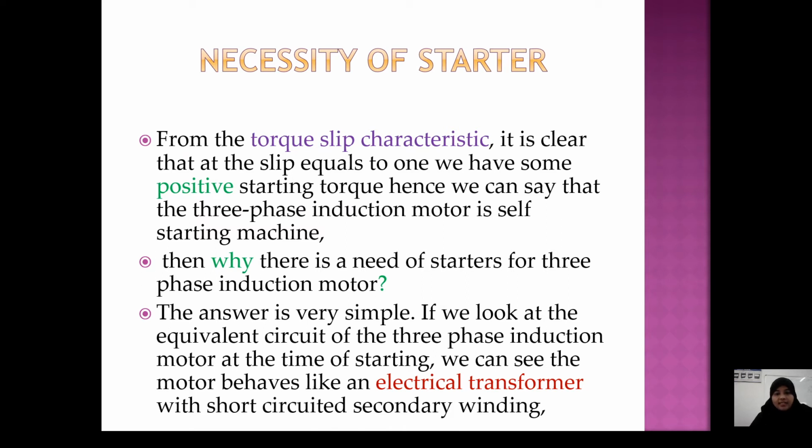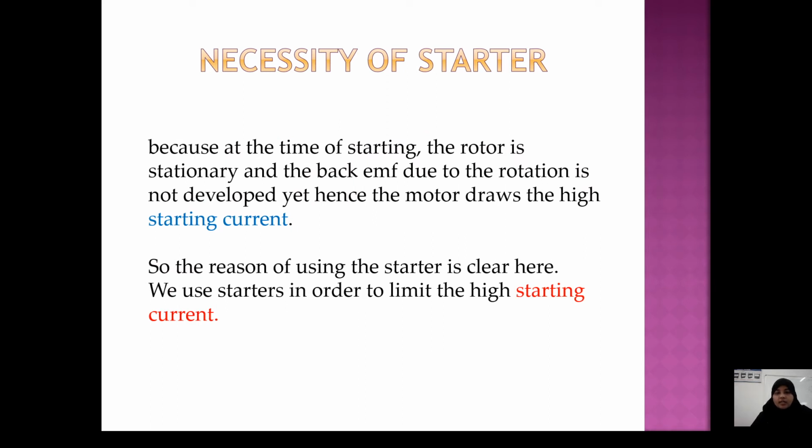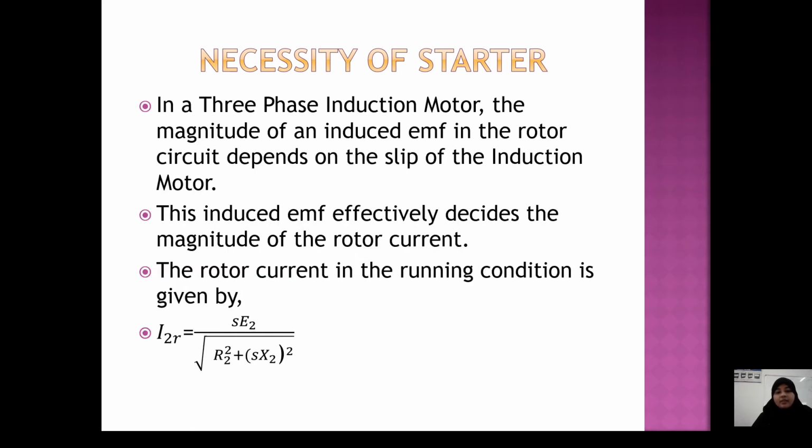So what we are saying here is that the induction motor will behave as a transformer whose rotor is short circuited. Secondary here implies rotor. So the current will be very high on the rotor side, and the stator will also take high current from the starting voltage. So to reduce this starting current we use a starter.